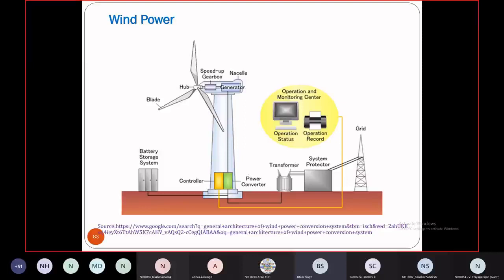So normally if we are using an induction machine like the doubly fed induction generator, we require a 3-stage gear to bring it to a speed of around 1500 RPM, the synchronous speed with a 4-pole machine, and the speed of the machine varies from 1000 to 2000 RPM with around 30% slip or so. In that case, the double converter is put in the rotor with power control. So you have a generator, you have the controller and power converter, and then you put a transformer, and then through protection it goes to the grid, typically with power control.